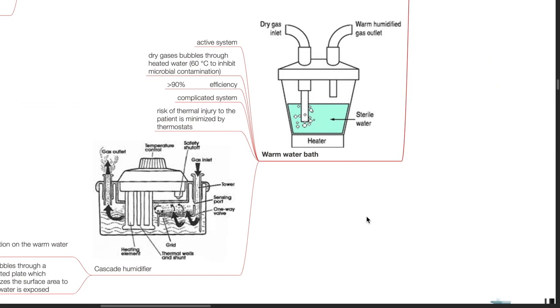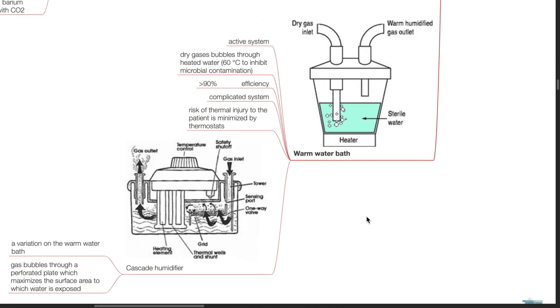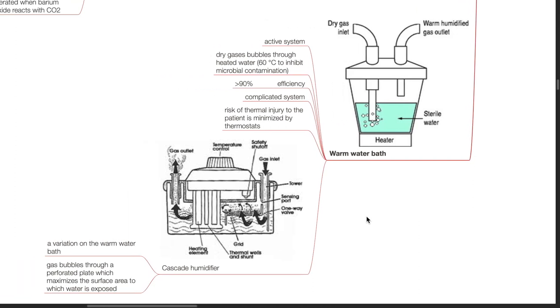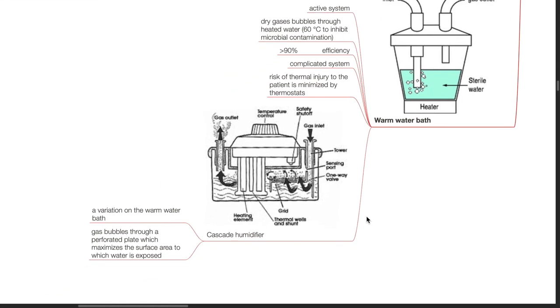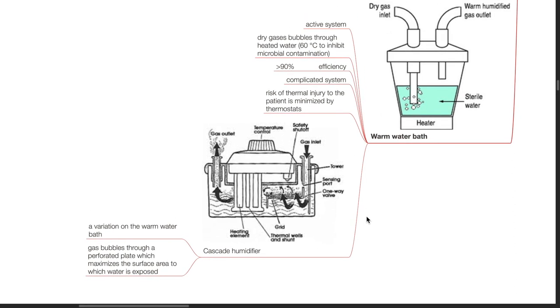Warm water bath: this is an active system. Dry gases bubble through heated water at 60 degrees Celsius to inhibit microbial contamination. Efficiency is more than 90%, though it is a complicated system. The risk of thermal injury to the patient is minimized by thermostats. The cascade humidifier is a variation on the warm water bath, where gas bubbles through a perforated plate which maximizes the surface area to which water is exposed.